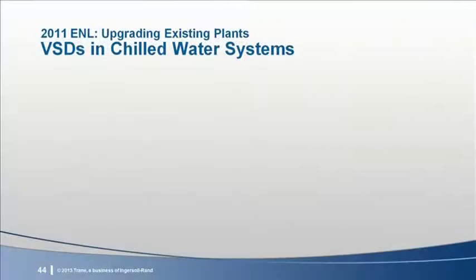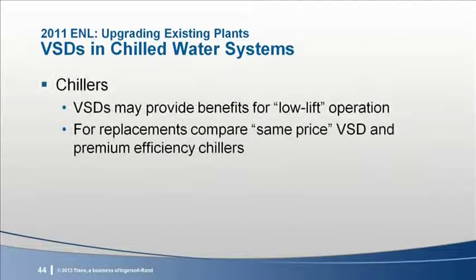Thanks, Lee. Let's fast forward 5 years. Here are some takeaways from our 2011 Engineers Newsletter Live on upgrading existing chilled water plants. Adding a variable speed drive to a centrifugal chiller benefits operation when there are enough operating hours at low lift conditions. For example, when the tower water temperature can be reduced.